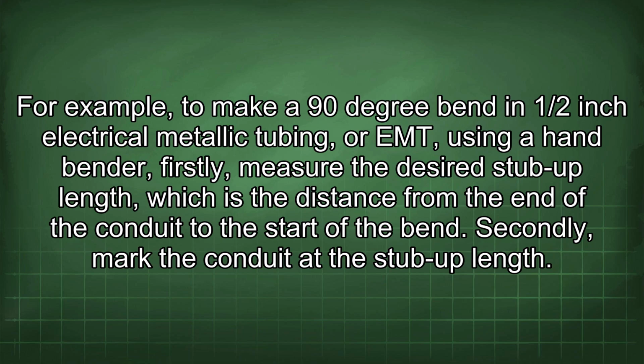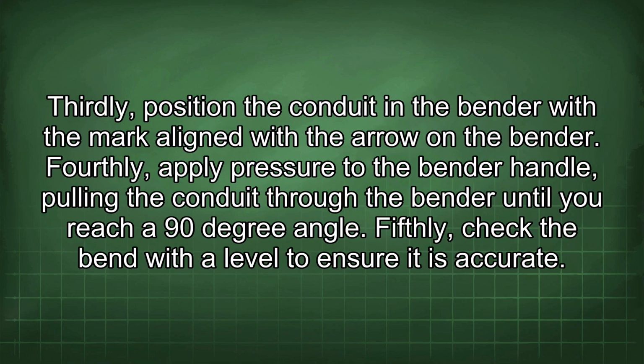For example, to make a 90-degree bend in 1/2 inch electrical metallic tubing, or EMT, using a hand bender, firstly, measure the desired stub-up length, which is the distance from the end of the conduit to the start of the bend. Secondly, mark the conduit at the stub-up. Thirdly, position the conduit in the bender with the mark aligned with the arrow on the bender. Fourthly, apply pressure to the bender handle, pulling the conduit through the bender until you reach a 90-degree angle. Fifthly, check the bend with a level to ensure it is accurate.